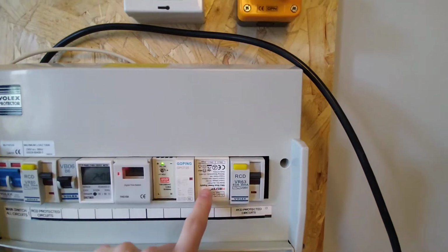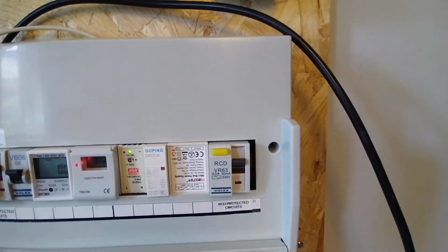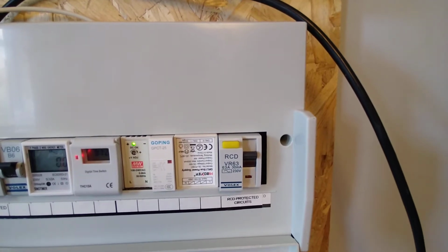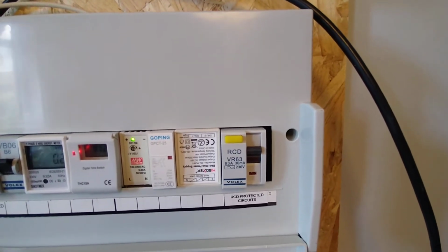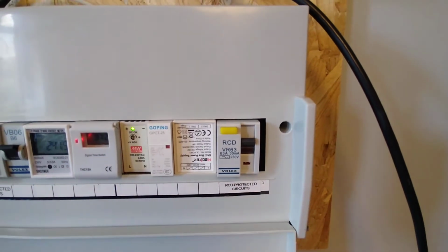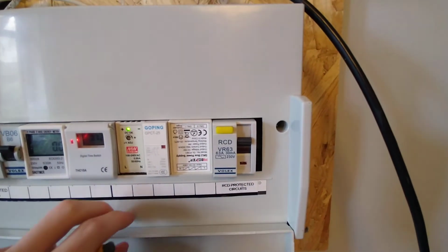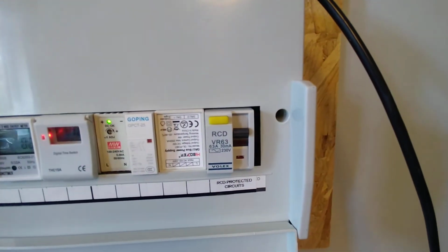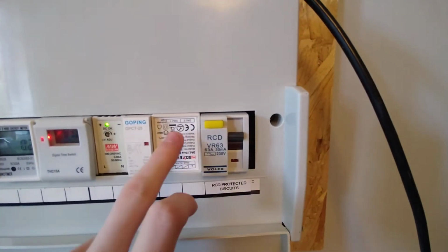The DALI power supply must be current limiting, because the way the bus operates, devices pull down the bus below a certain threshold to register 1 or 0. So they actually modulate the bus by pulling the bus down, bringing the voltage of the bus down to send data. So that's your DALI power supply.